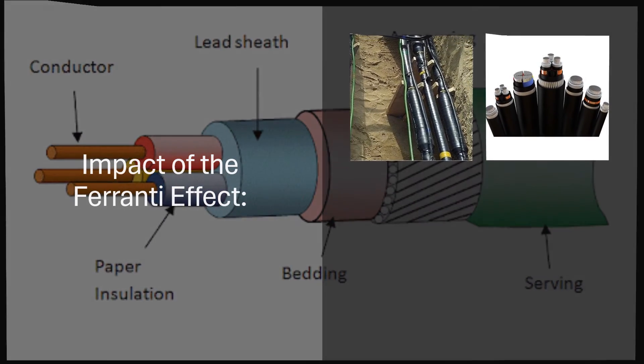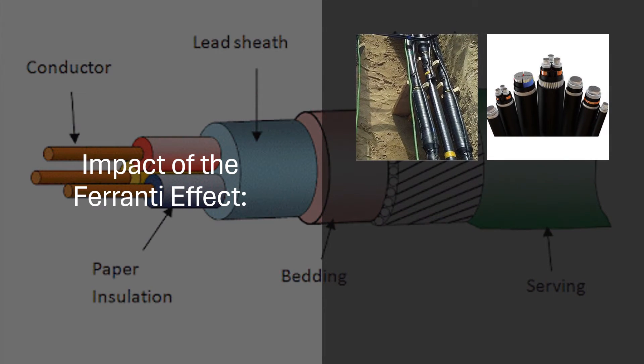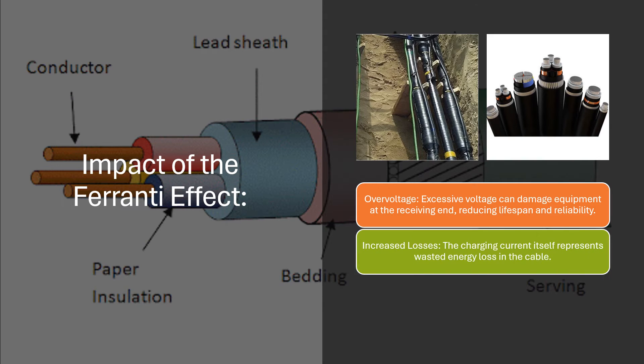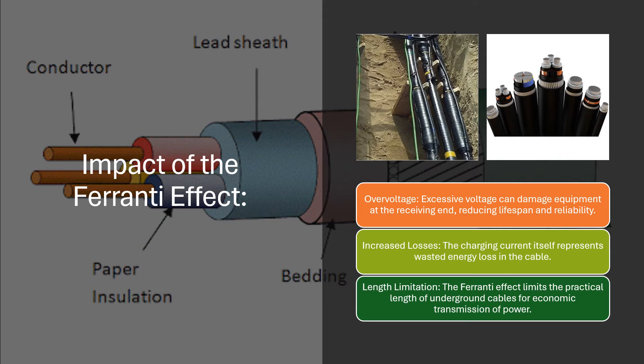Impact of the Ferranti effect. Overvoltage: excessive voltage can damage equipment at the receiving end, reducing lifespan and reliability. Increased losses: the charging current itself represents wasted energy loss in the cable. Length limitation: the Ferranti effect limits the practical length of underground cables for economic transmission of power.